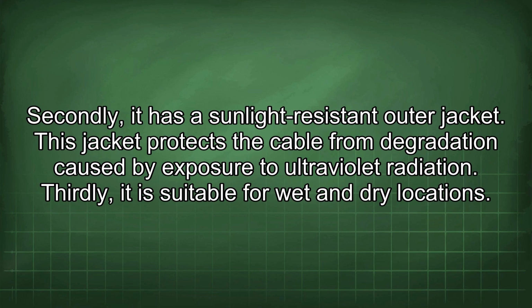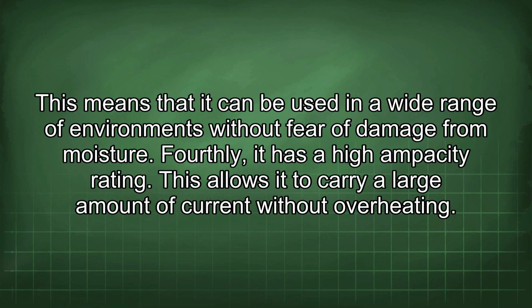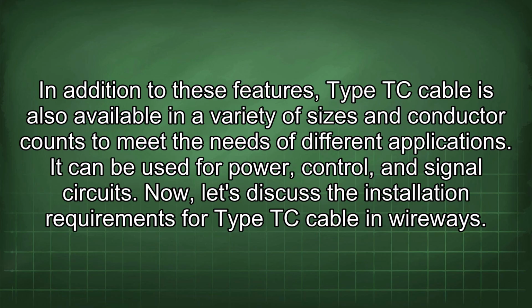Thirdly, it is suitable for wet and dry locations. This means that it can be used in a wide range of environments without fear of damage from moisture. Fourthly, it has a high ampacity rating. This allows it to carry a large amount of current without overheating. In addition to these features, Type TC cable is also available in a variety of sizes and conductor counts to meet the needs of different applications. It can be used for power, control, and signal circuits.